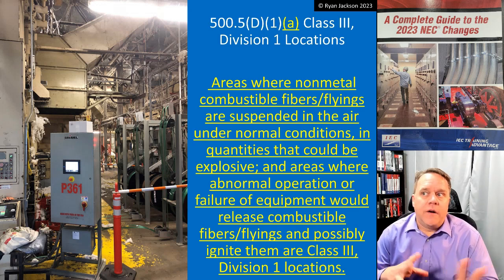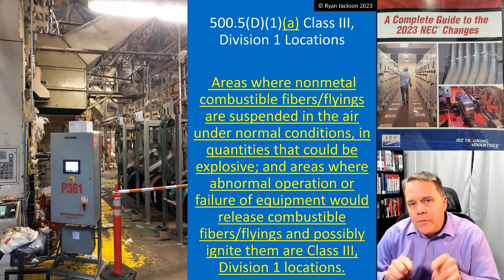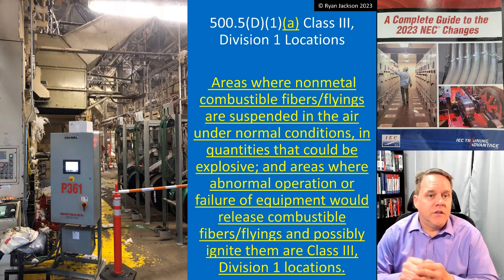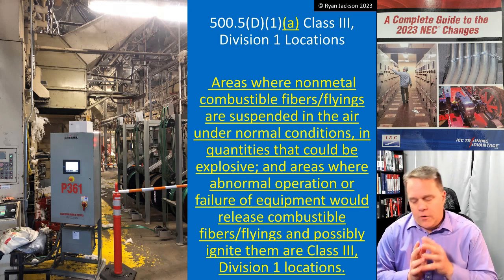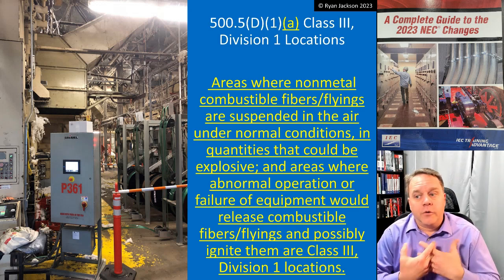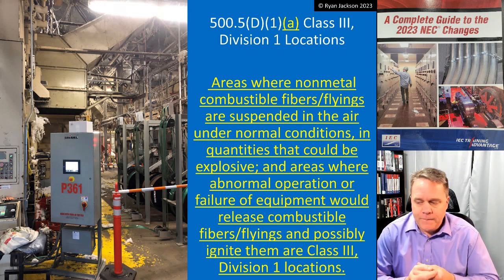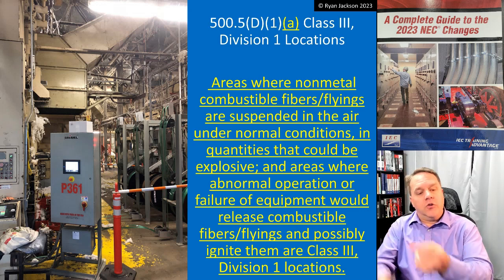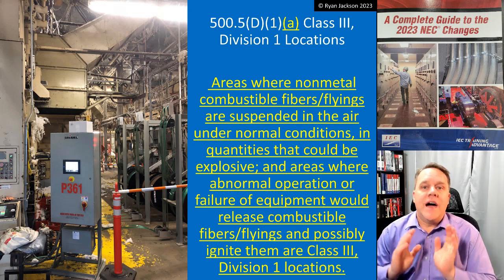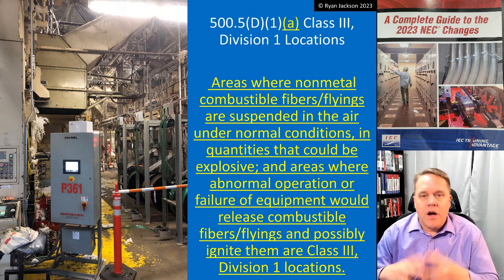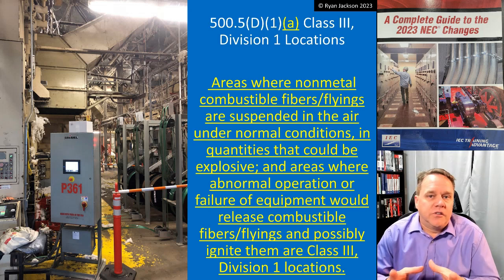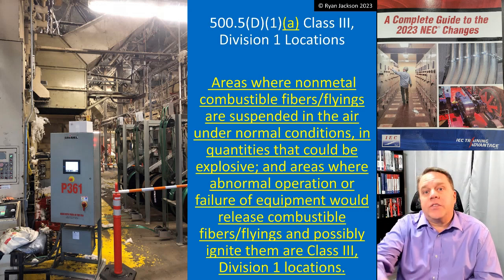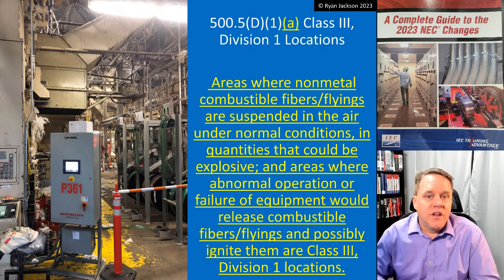The big thing is: what is the normal condition? For example, sanding wood creates combustible dust. The difference between combustible dust and combustible fibers and flyings is simply the size of the solid material. On a wood lathe, if you're doing it right, you get streamers of wood shooting over your shoulders — that is much bigger than combustible dust, and that would be an example of a fiber or flying.